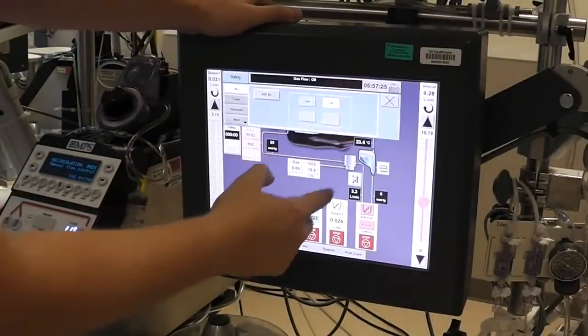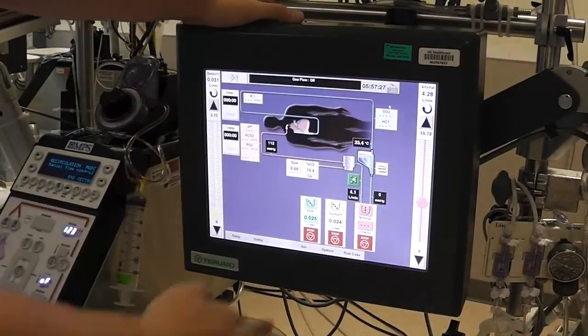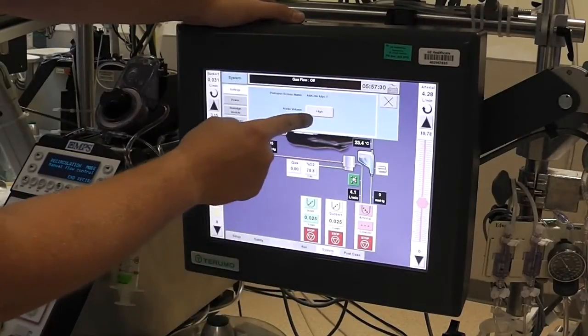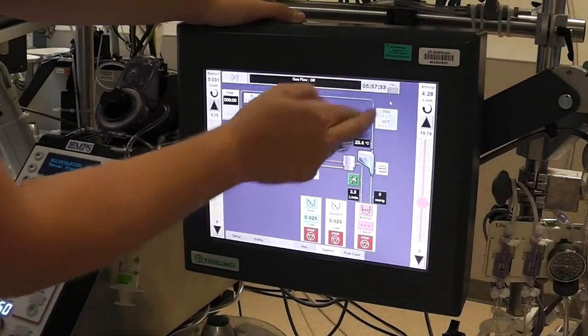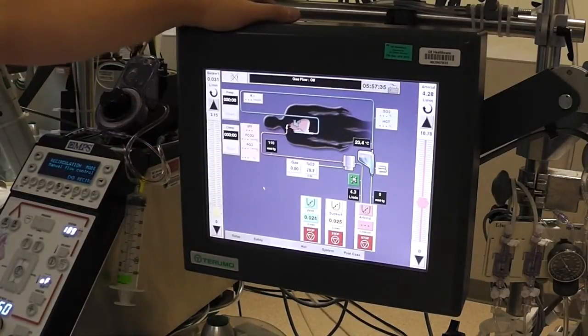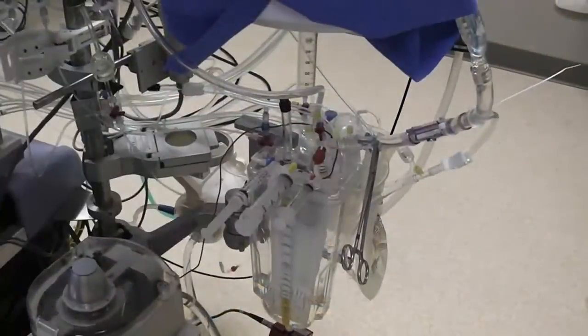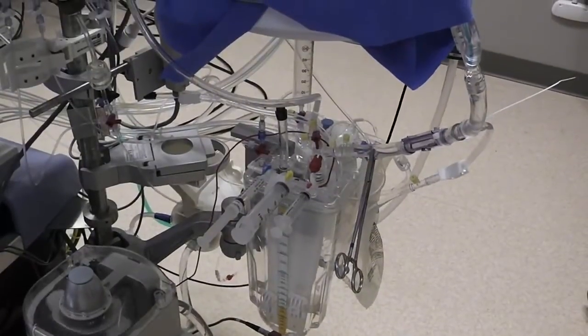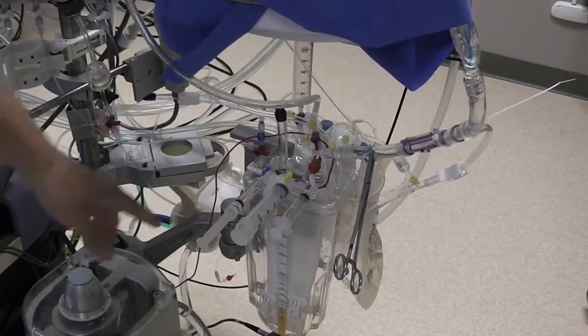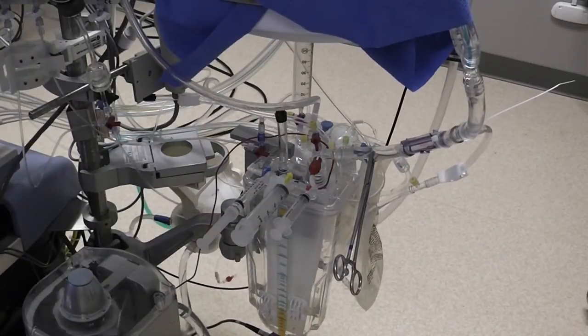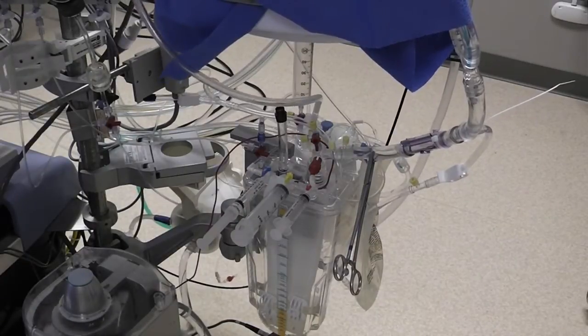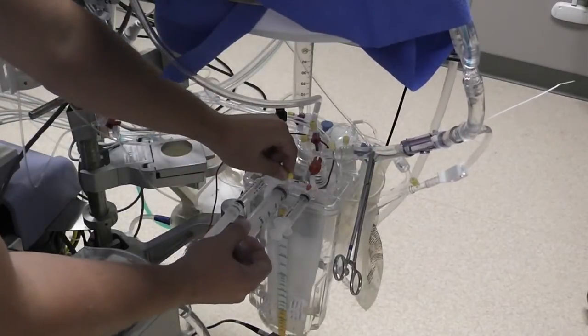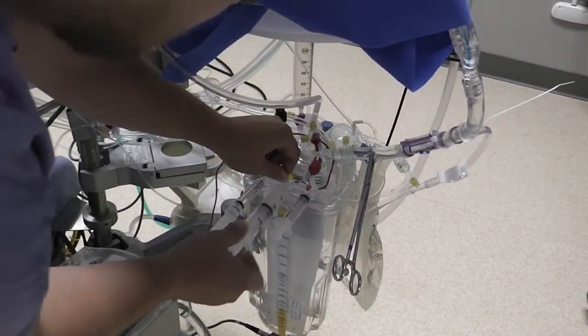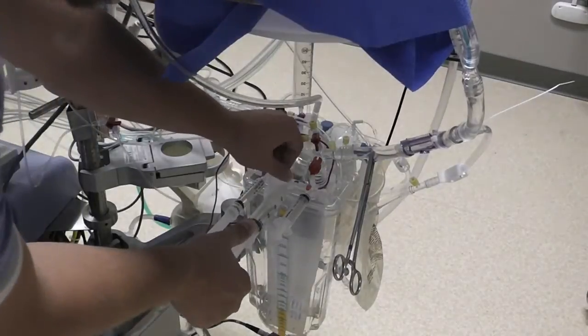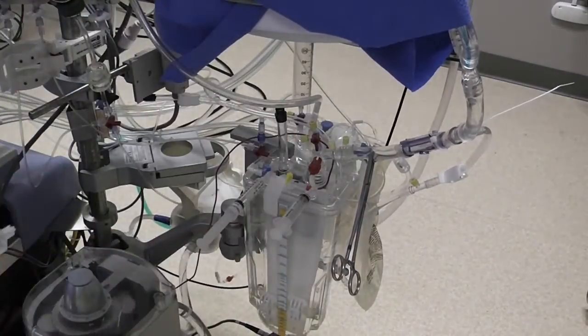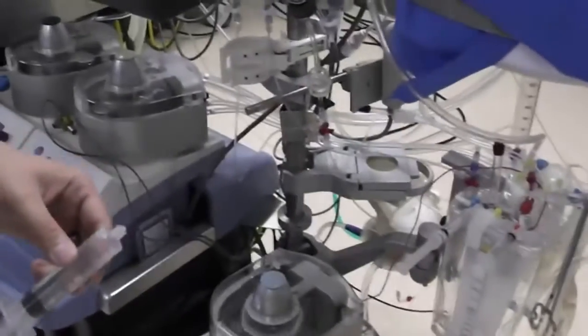On the pump, make sure you have your bubble detector turned on, and hit the system down here to turn the audio volume down to low by tapping that twice. It just prevents the alarms from being crazy loud. One thing you will need if you have retrograde is a 30cc syringe filled with fluid. You can either put a needle on the syringe and draw it up from the bag, or you can take it off the manifold here. And normally you do this before you have drugs in, obviously. But then this will go on the top.